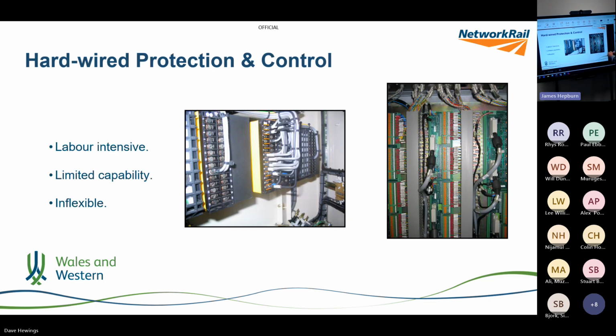That's a typical back of a protection panel in a conventional substation - wires for everything, a pair of wires for every single function, and another pair of wires for every other function. But once you've wired it, that's it. If you want to change the functionality, you have to go rewire it. Whereas, of course, in any other walk of life, that would now be done by data flows.